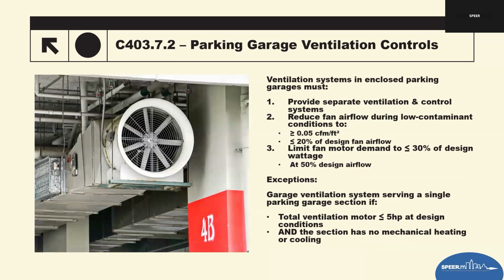Parking garage ventilation controls. They continue to keep updating this as well. C403.7.2 covers ventilation energy controls specifically for enclosed parking spaces. So these spaces often have large fans that run continuously. The 24 requires better control strategies to reduce energy use when contamination levels are low. So when there's very few cars in there, things of that nature, that's going to actually reduce the fan run.